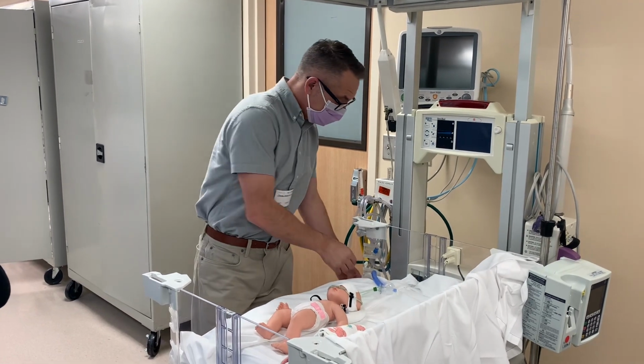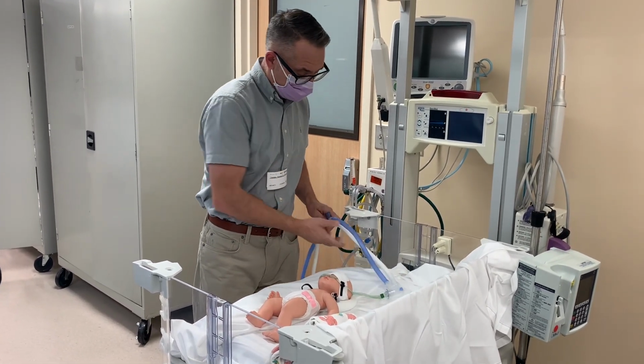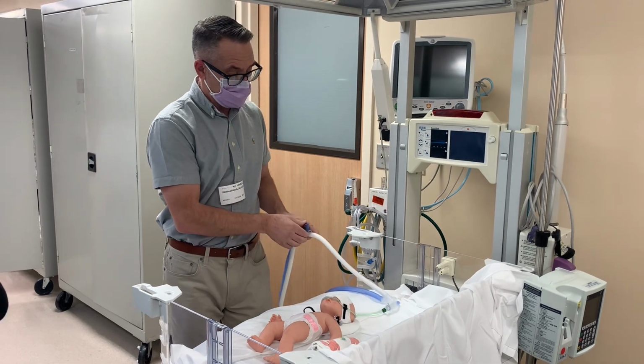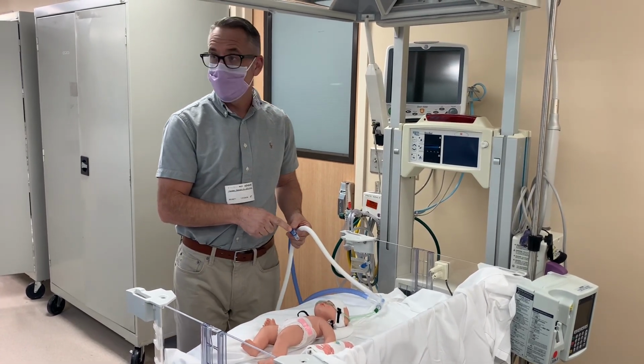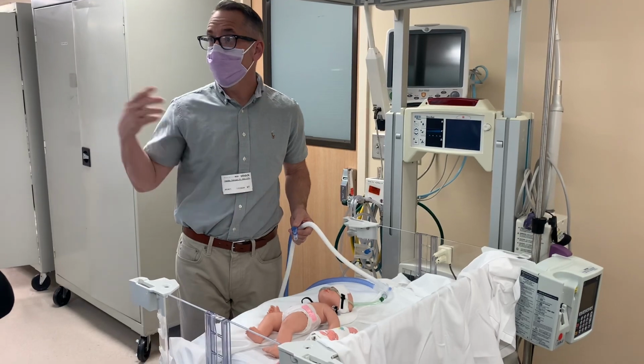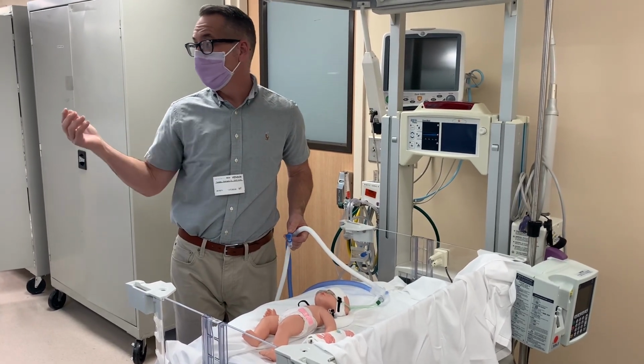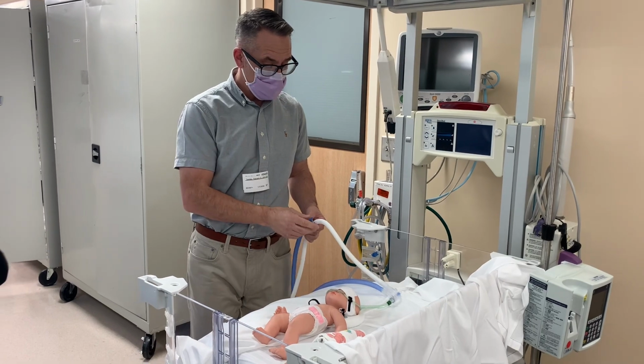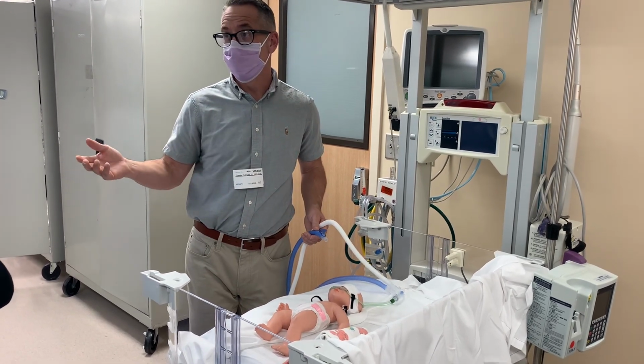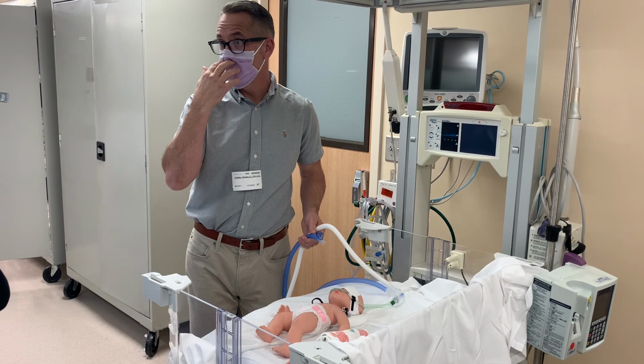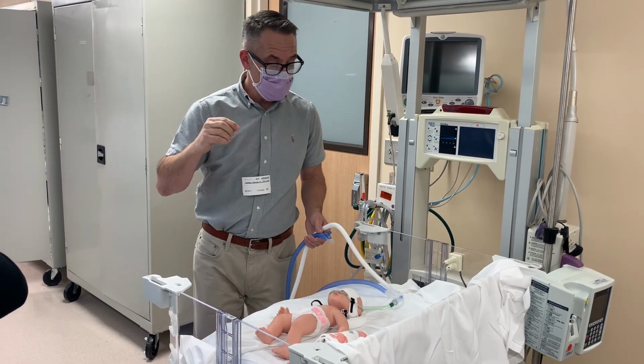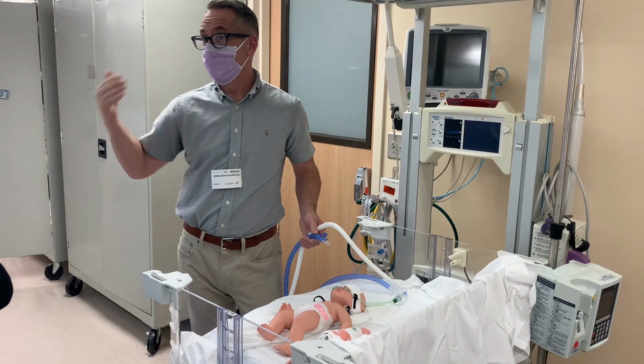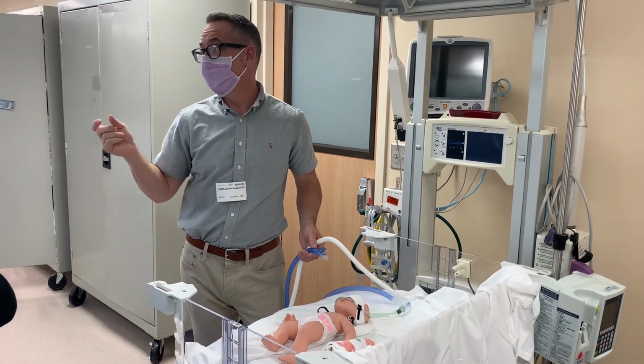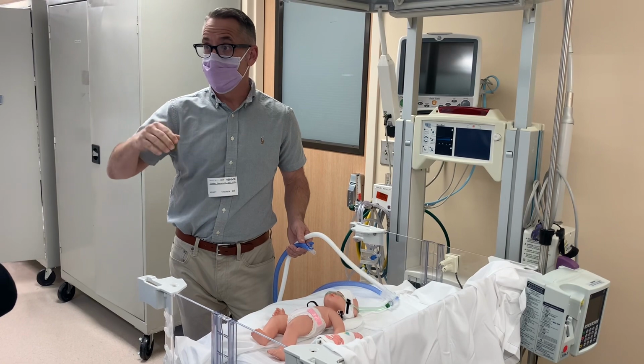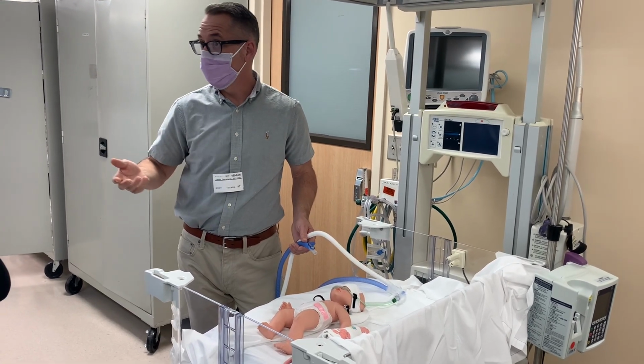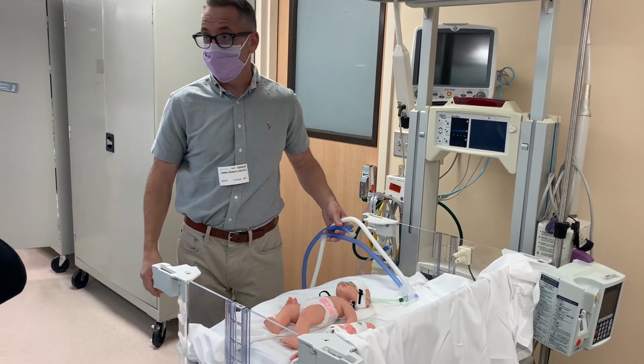Number two, the way these inspiratory limbs are designed is the temperature when the air comes out here is 40 degrees, because every 2 inches, the air cools by 1 degree. The problem is that when it's used on a Fisher and Paykel interface, that's already incorporated, so you get 37 degrees to the baby. The other problem is that if the temperature drops below 37, then we hit that dew point threshold. And so every degree that's dropping, more and more rainout is building up. So we have two things that are causing a great deal of rainout.